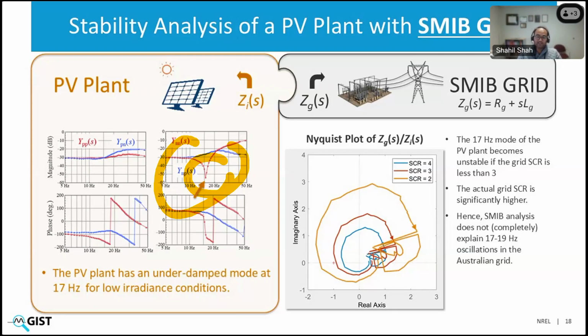And then we plot the Nyquist plot of impedance ratio for different SCR conditions, or for different grid strength conditions. And we find out that for SCR of less than 3, the Nyquist plot encircles the critical point, basically this -1 point, and that shows instability. So what this tells us is that this PV plant will become unstable under low irradiance condition if the grid SCR is less than 3.